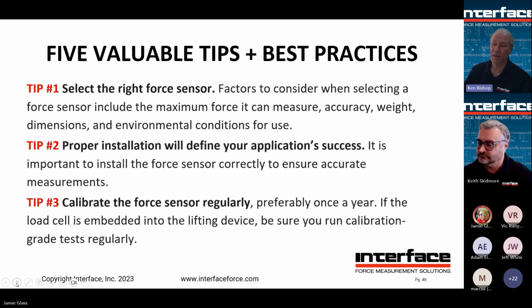Recommended once a year, but it depends, right? If you're doing something during the lift, and something happened that shifted the load and put an unusual shock on the load cell, and you're questioning whether something happened to that load cell or to that load shackle or load pin, we recommend that you get that in right away for an evaluation. And if it's a critical situation, you should really have a backup sensor nearby, because you don't want to shut down your operation because you didn't have a backup piece of equipment there.